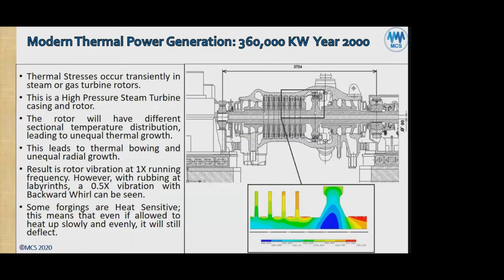Modern thermal power plants are still experiencing troubles with thermal transient vibrations and thermal transient stresses. Obviously, thermal transient stresses caused by unequal temperatures will also cause thermal transient vibration because the mass has changed with regard to the center of geometry of the rotor due to thermal transients.